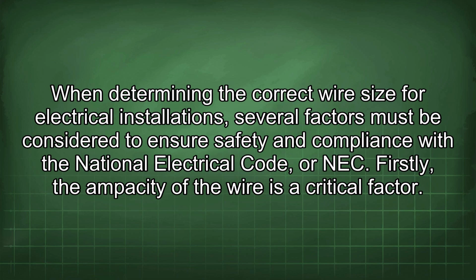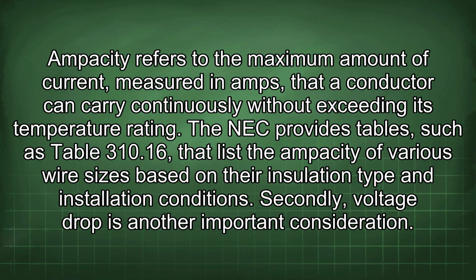Firstly, the ampacity of the wire is a critical factor. Ampacity refers to the maximum amount of current, measured in amps, that a conductor can carry continuously without exceeding its temperature rating. The NEC provides tables, such as Table 310.16, that list the ampacity of various wire sizes based on their insulation type and installation conditions.